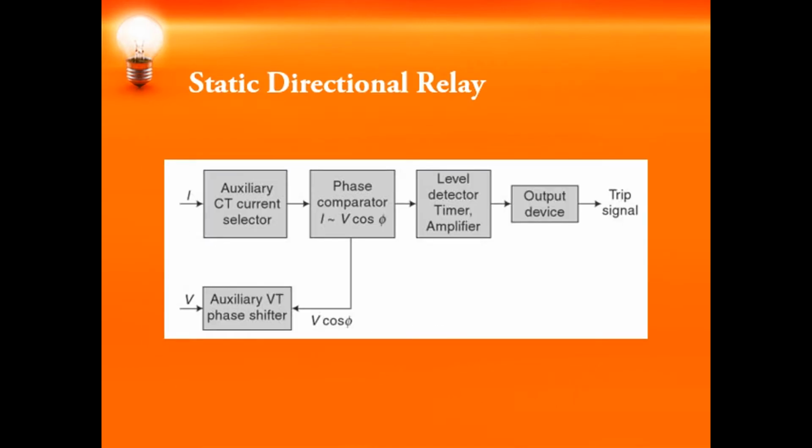In these directional type relays, we use a directional element along with the normal components. In static type relays, as I told you, you have a comparator, or nothing but a level detector, wherein the comparator can compare either the magnitude of the electrical quantity or the phase angle of the electrical quantity. Here we are mainly concentrating on current. When it is the phase that is going to be measured, we measure the angle difference between the voltage and current. That is what is done here.